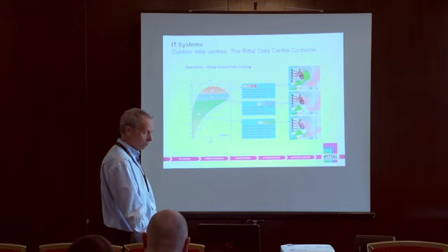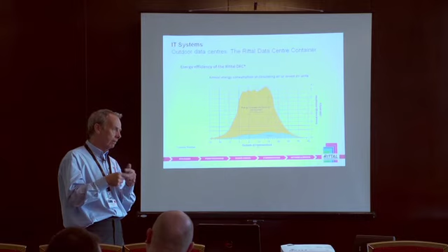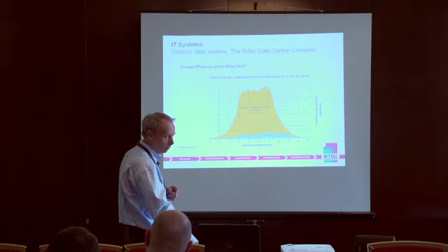If you look at the bottom, we're quite near the bottom on this. What we tend to use now to assist in our cooling procedures is a monitoring system which evaluates the heat generation in a rack. Our higher cooling solutions are based around six EC fans, so variable speed. The monitoring system analyses the air all the way up and down the rack, takes in that information, and then speeds the relevant fans up or slows them down as necessary. The fans are also hot swappable, which makes life a little more interesting.